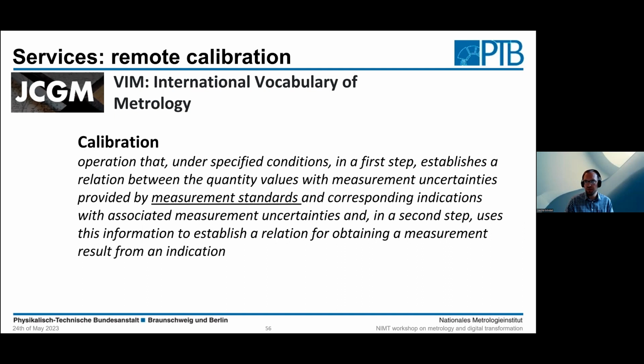So if you want to do remote calibration of any kind, you have to find a way to provide a measurement standard remotely. There are examples where you can build it in, like there are temperature sensors that have a built-in reference with a known melting point, for instance, that you can use then to recalibrate the sensor. In other areas, it may be much more complicated, like for a weighing instrument, for instance. How do you derive a remote measurement standard? So if you want to provide services for remote calibration, you need to have a definition of what is the measurement standard for that service and how do I make this remotely accessible.